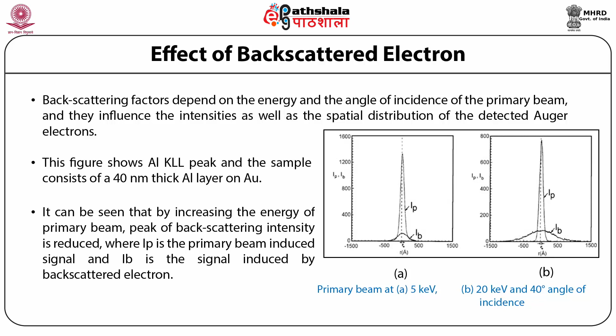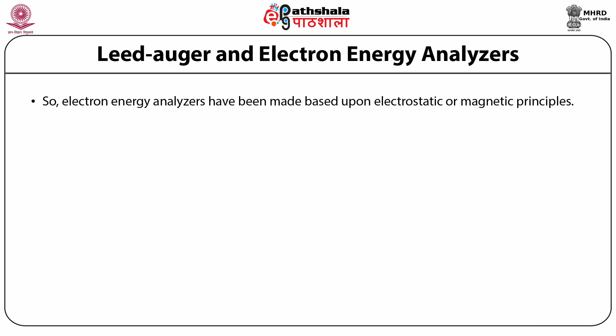Auger electron spectroscopy utilizes analyzers to analyze electrons. Here we will discuss these in brief only. Electron energy analyzers have been made upon an electrostatic or magnetic principle. Although magnetic instruments with high resolution, that is of the order of 10 meV or better, have been constructed, these will not be discussed here due to their complexity and stringent requirements on magnetic shielding. There are two classes of electrostatic analyzers: the dispersive and the retarding field.